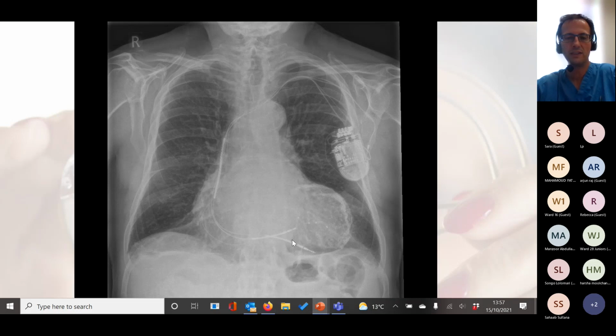And you can see there are 2 leads in the ventricle, and that's because one lead has failed long ago and they've had to have a replacement lead put in. Now, can you see how clear this thick defibrillator coil is on the leads? The appearance of the leads is uniform, and then suddenly this thick coil. If this was a pacemaker lead, it would look like the uniform bit all the way to the end. You'd see this pole and the tip right at the very end.